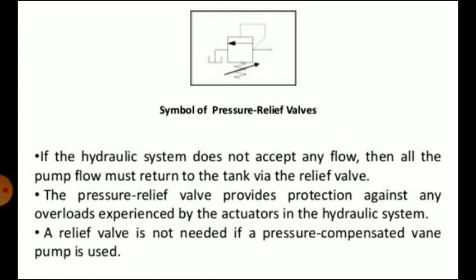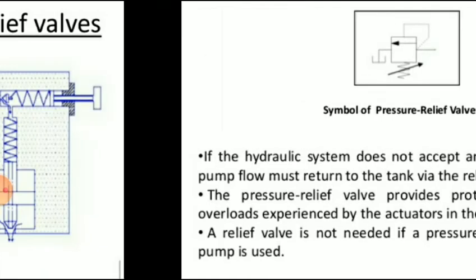If the hydraulic system does not accept any flow, then all the pump flow must return to the tank via the relief valve. The pressure relief valve provides protection against any overloads experienced by the actuators in a hydraulic system. A relief valve is not needed if a pressure compensated pump is used.